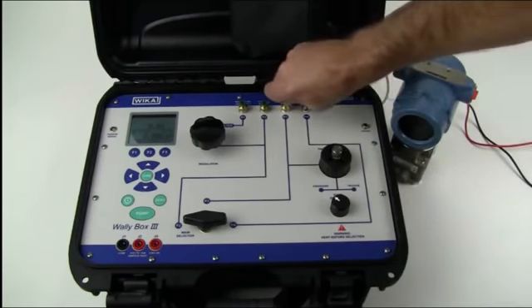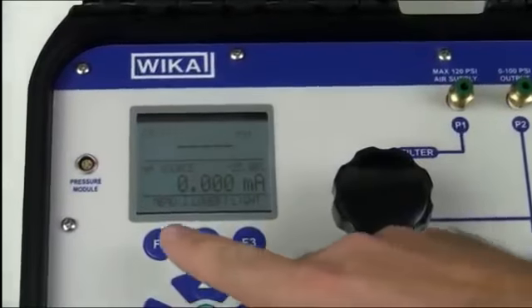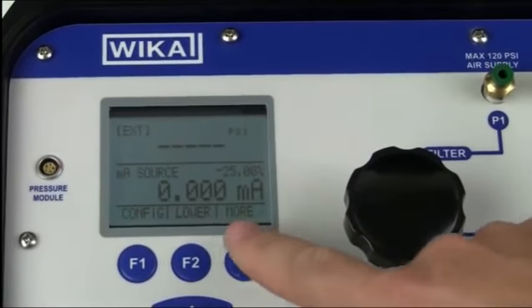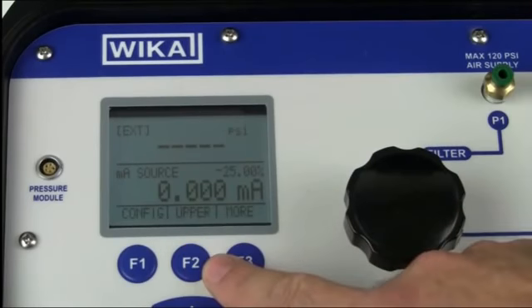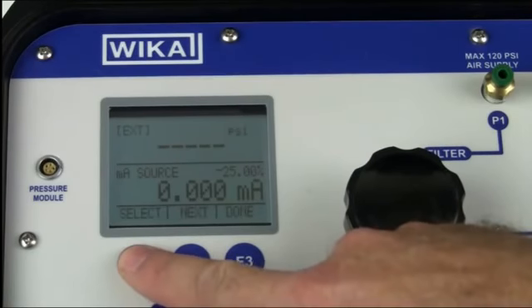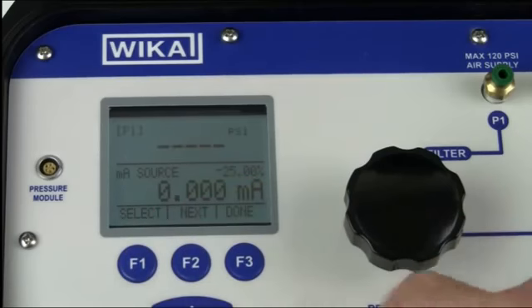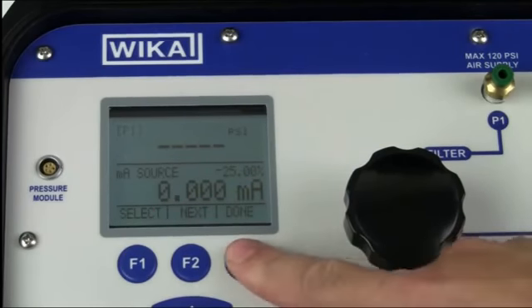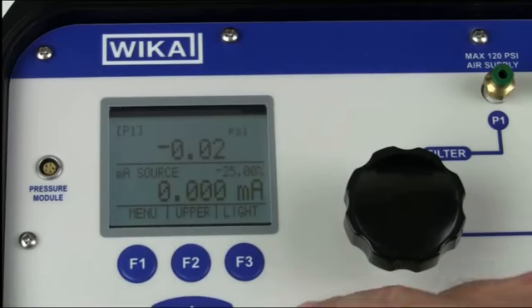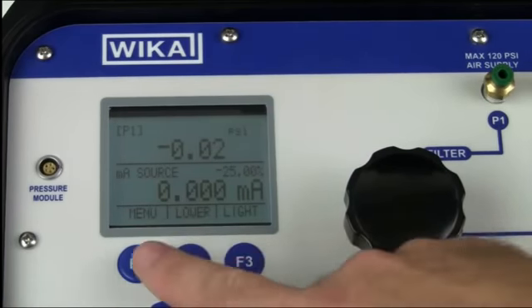Now we need to set up the display so that it suits the test we want to perform. We hit the menu tab, then we will make sure we select the upper display, then configuring the upper display so that it measures P1, which is the internal pressure sensor. We then select done. We now need to select the bottom display. We select the bottom display. We need it to do milliamps, which has already been done. However, we need to make sure that it's in the 24 volt measure configuration. We hit done and we're now ready to perform our test.